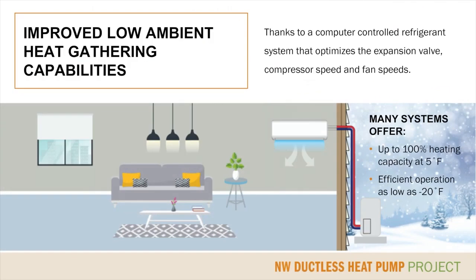The current generation of modern, extended capacity heat pumps is what we're focused on here today. These heat pumps have computers inside, specifically programmed to independently control fan motors, compressors, and electronic expansion valves. They are called by a lot of different names, but utility programs call them cold climate variable capacity heat pumps. Most of the major brands have models that can produce 100% of their rated capacity down to 5 degrees Fahrenheit. They can also produce heat efficiently down to as low as -20 degrees Fahrenheit. They are nothing short of amazing.